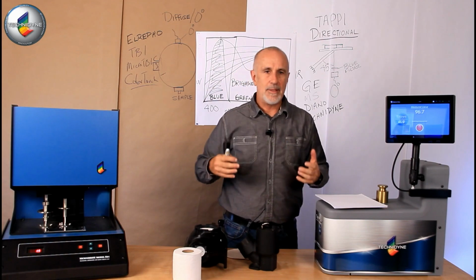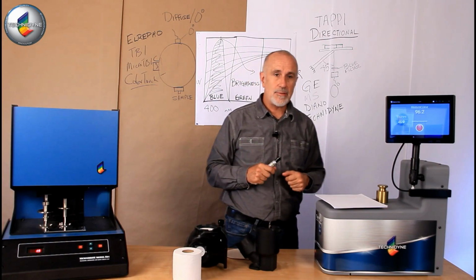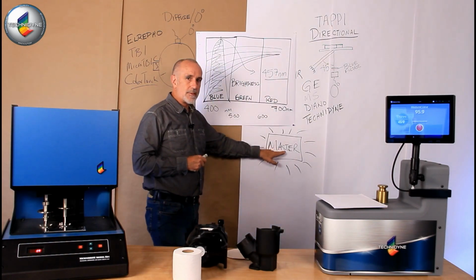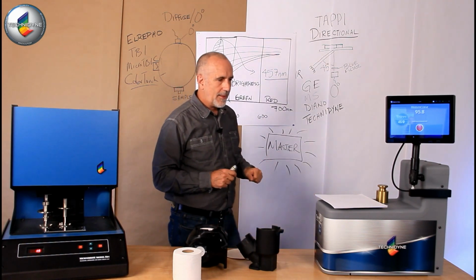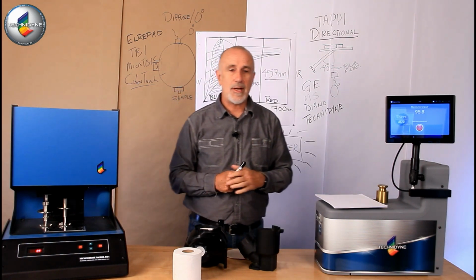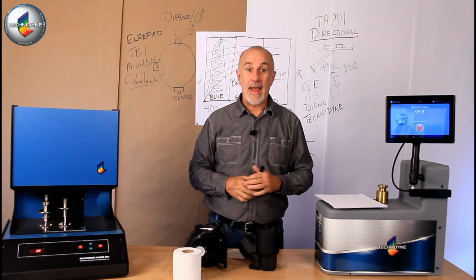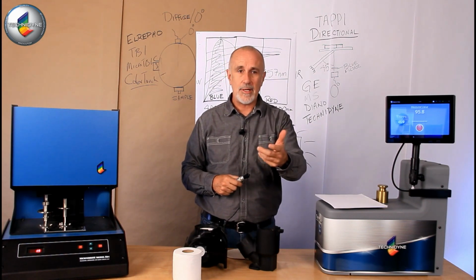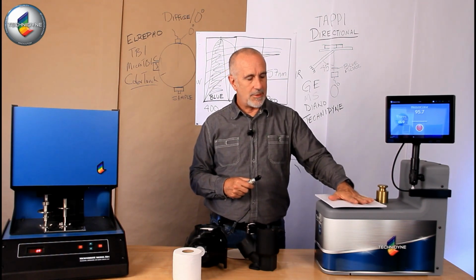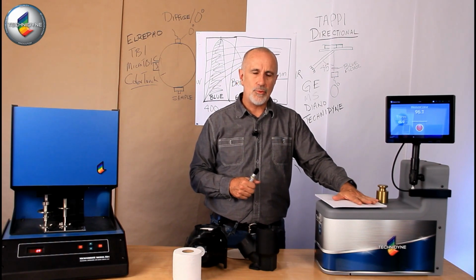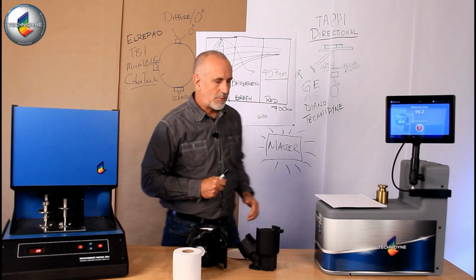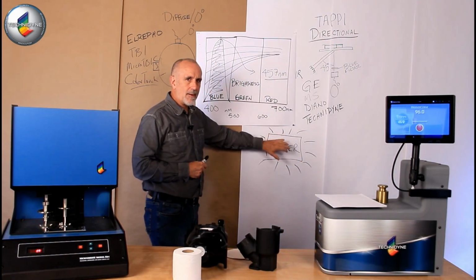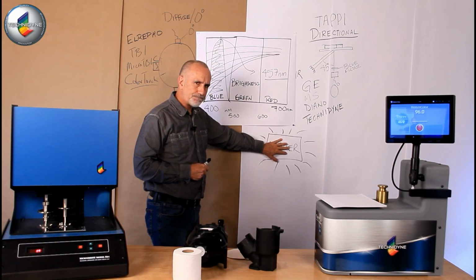So it's our job in maintaining the master laboratory instruments to make sure that this point does not drift. We have a lot of checks and balances in our processes to make sure that we have an anchor at that point for calibration. So the sequence in the TAPPI method is pretty simple. It's to bring instruments into agreement with a master instrument back in our master's laboratory.